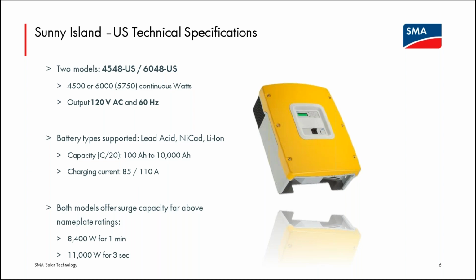That is a monstrous battery. That is a battery room. That is not a battery bank. So that is a huge, huge battery. And again, these are just suggested ranges. The Sunny Island can turn on with a much smaller capacity battery bank, as long as it has a stable 48 volts. But if it has to cycle that battery bank repeatedly within a day, the lifetime of that battery will be very short. So the lowest rational size for any real system, we think, is around 100 amp hours.